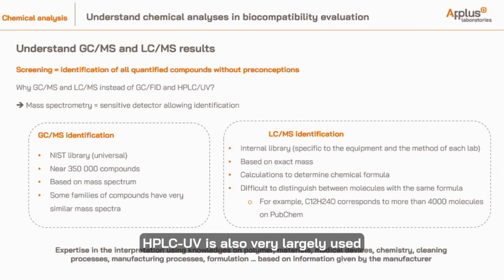HPLC-UV is also very largely used in the chemical field, but the UV detector is not universal and is not very sensitive. So it's not possible with these detectors to go further in identification of compounds. We need to know the compound that we are looking for. And this is not the case for extractables studies. In these studies, we perform screening, and by screening, we mean that we will identify all detected compounds without preconceptions. We need to understand what we see, but we are not looking especially for a list of compounds.